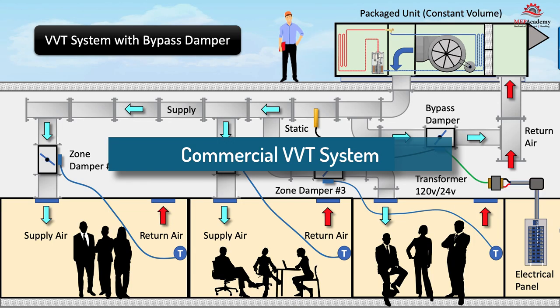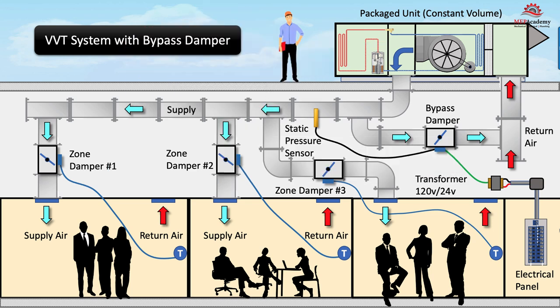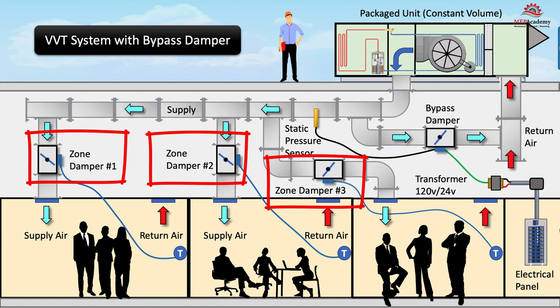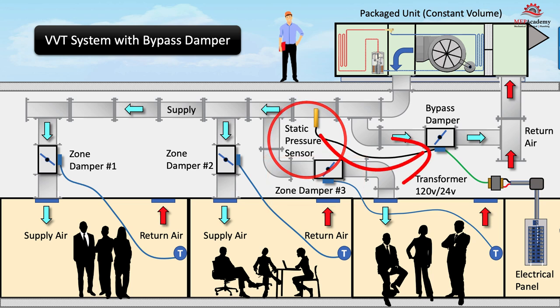In a commercial VVT system with a bypass damper, the constant volume air conditioner or heat pump serves several zones, with each zone having their own zone damper and controller. When the zone dampers start to close, a static pressure sensor picks up an increase in the duct static pressure and sends a signal to the bypass damper controller to modulate the damper open.